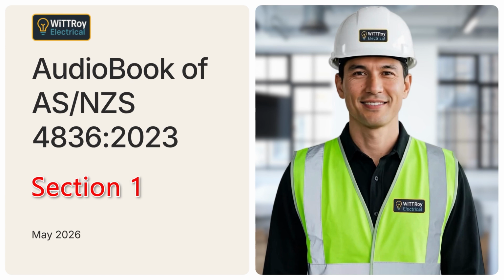1.29.2 Work on. Work on means doing a task within 500 millimeters of exposed energized conductors or live conductive parts or electrical equipment. This includes work such as constructing, installing, connecting, maintaining, repairing, altering, testing, verifying, assessing, inspecting, removing, or adding to an installation or equipment. In simple terms, this is the closer and higher risk work zone.